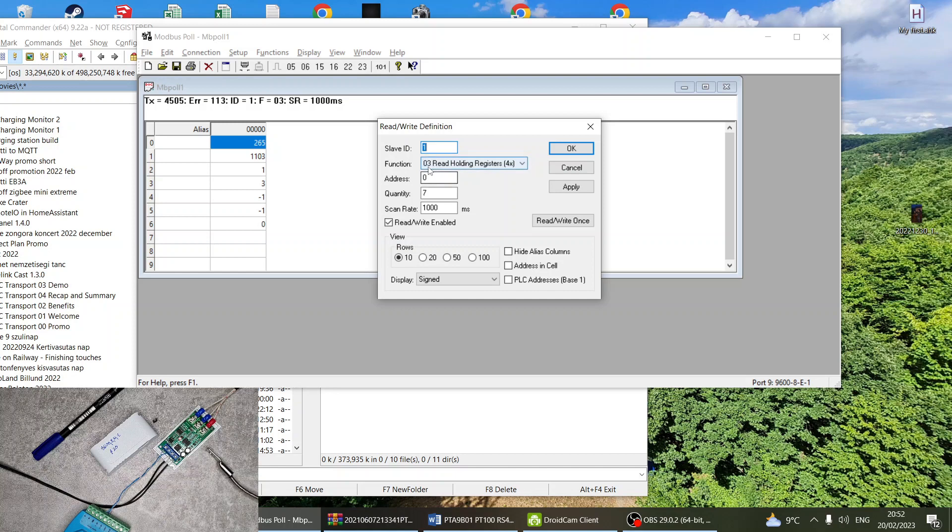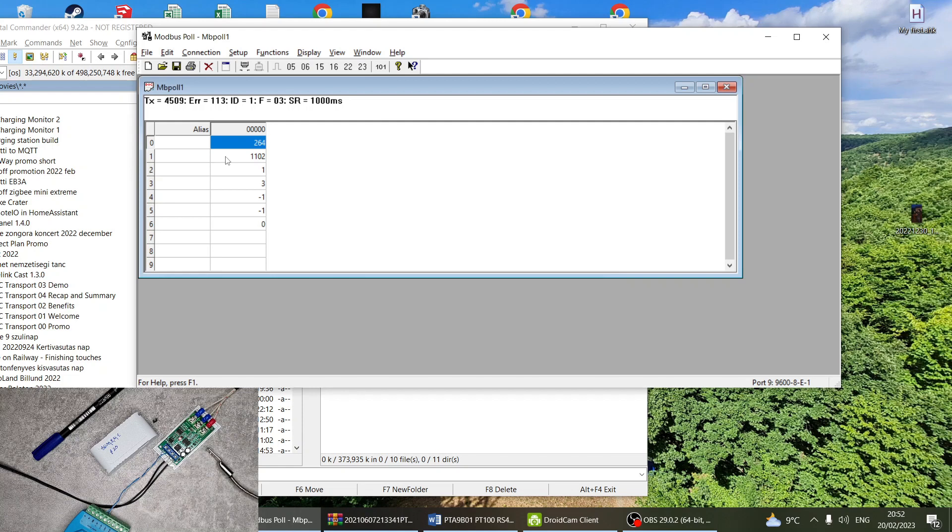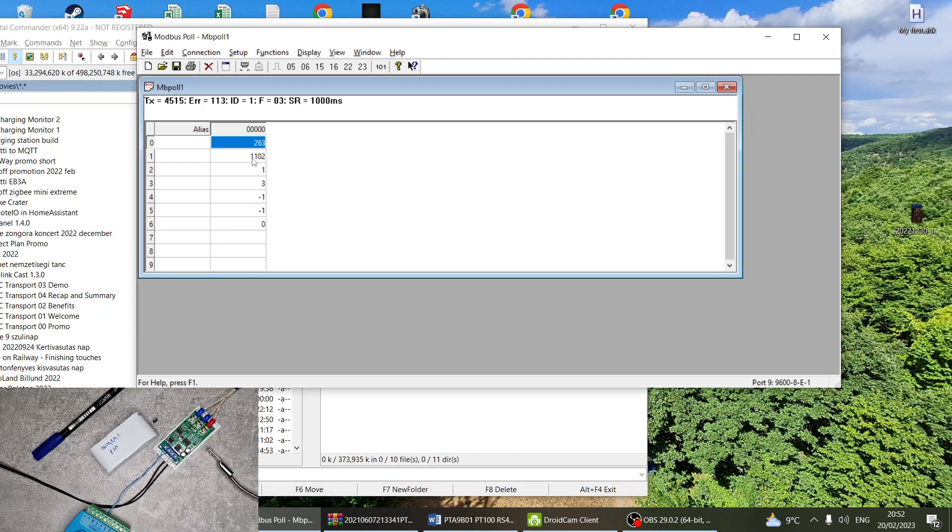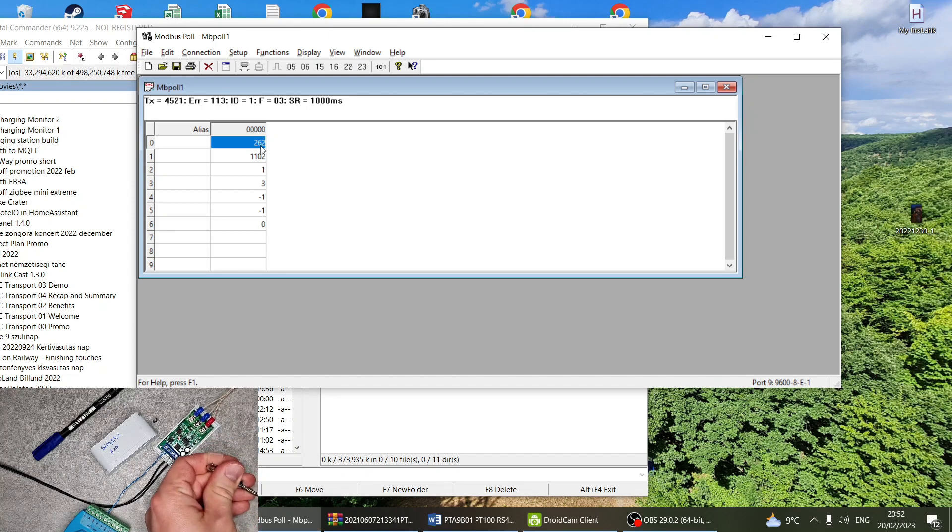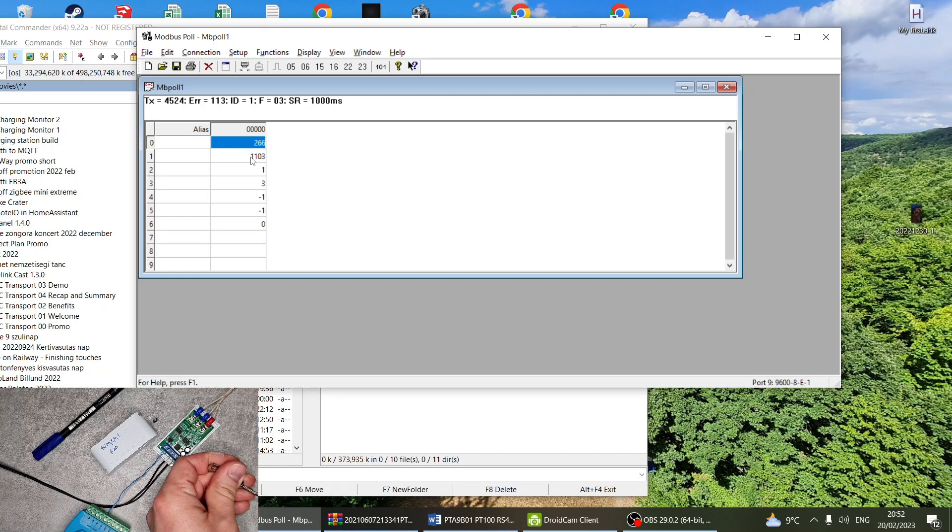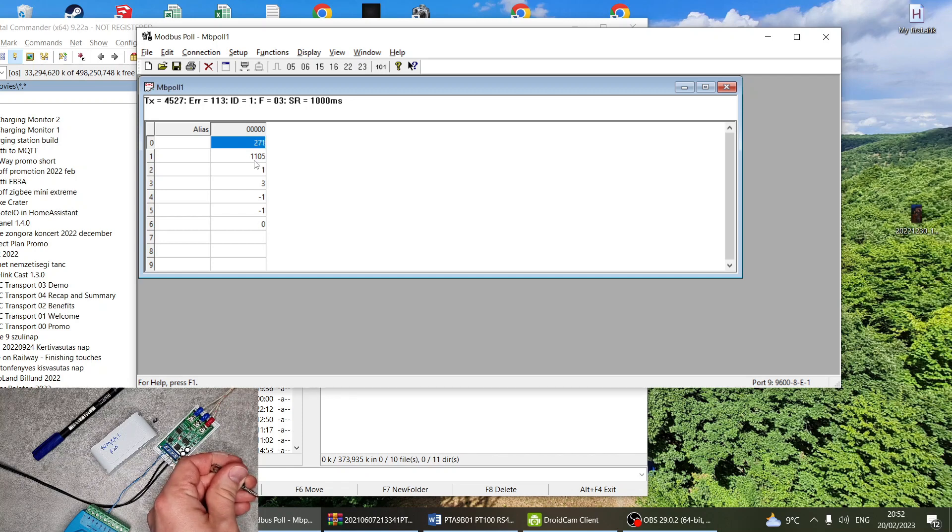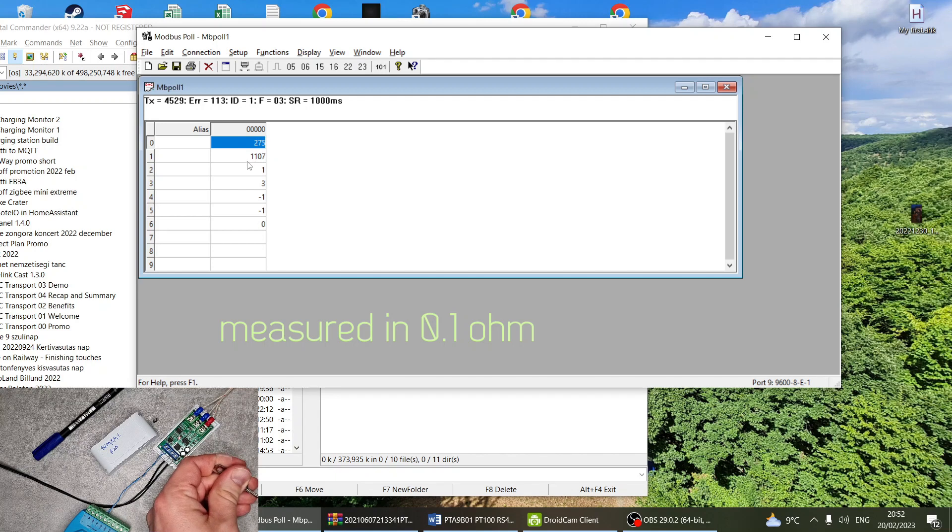Everything is stored in holding registers, so what I did here is I'm reading holding registers from address 0 and I'm reading seven registers. You can see that the first value is the temperature, so that's measuring in Celsius, that's 26.2 degrees. Of course if I touch it then we can see the temperature go up. The second one is the actual resistance which is measured by the unit, so that's the resistance of the PT100 element.